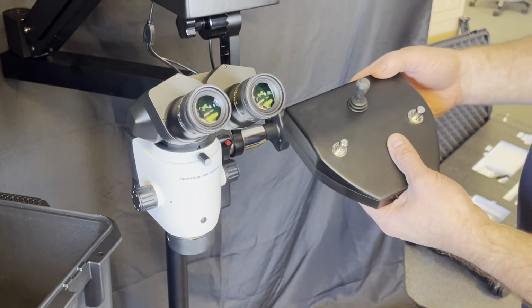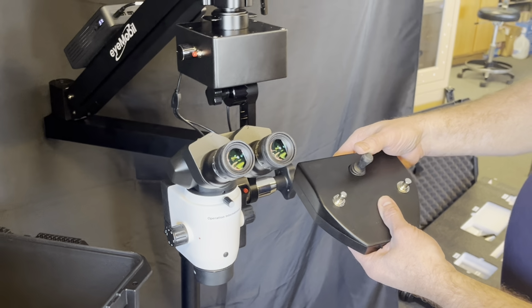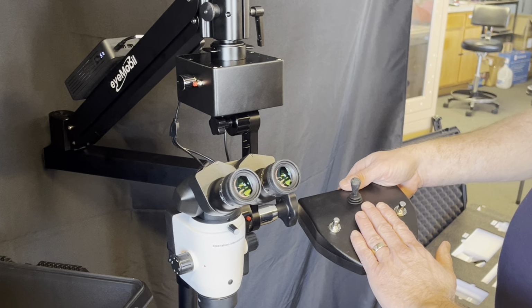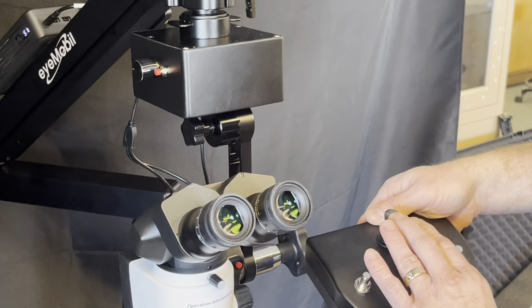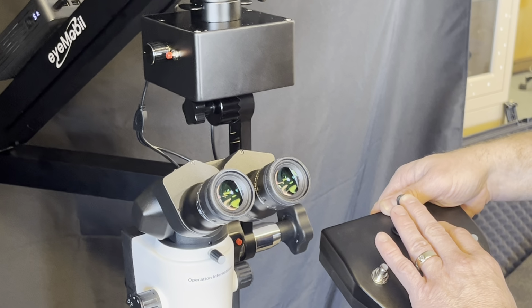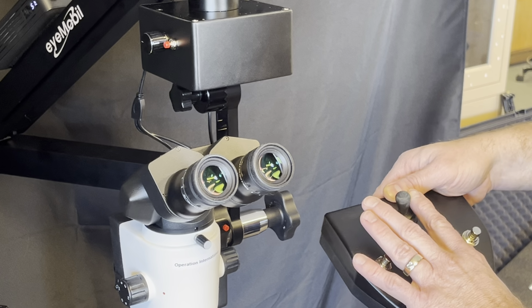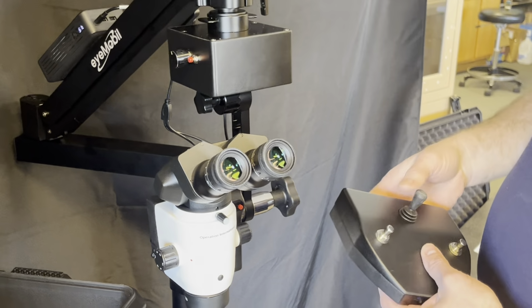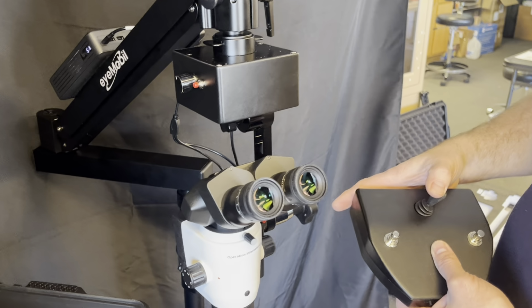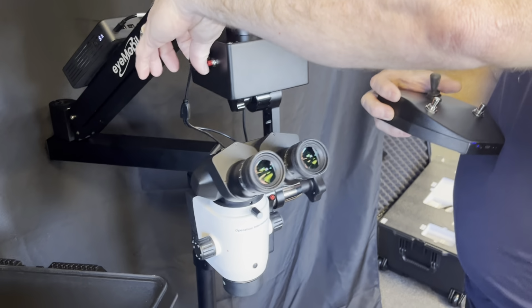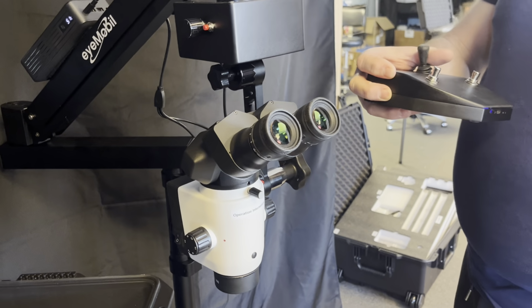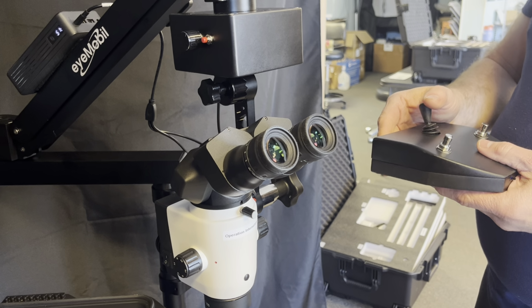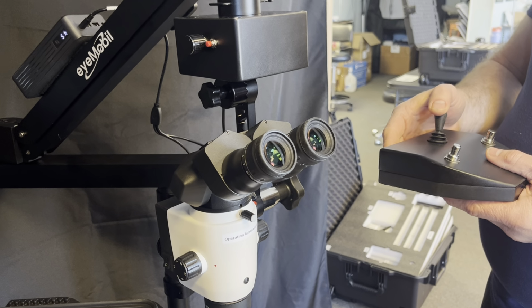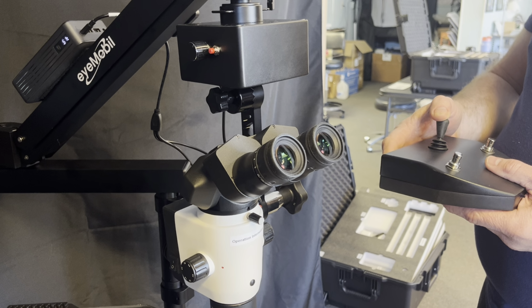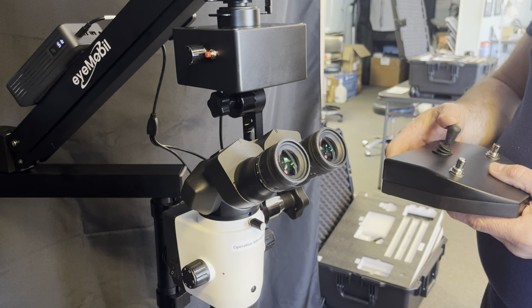Now for the function of the XY unit. It's a standard joystick where the surgeon rests their foot here, pulling down on the joystick this way brings the scope towards you, pushing up goes away, left and right. And our XY unit also has speed control. So this is maximum speed, and I'll show you now minimum speed. So it's very slow, particularly if you're really working on a high level of magnification. This slowest speed is very helpful.